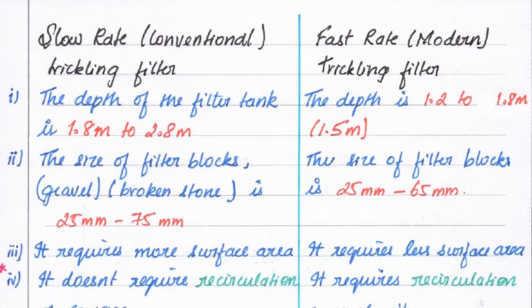In the slow rate trickling filter, the depth of the filter tank should be 1.8 meters to 2.8 meters. In the fast rate trickling filter, the depth is 1.2 to 1.8 meters, with a mean depth of 1.5 meters.